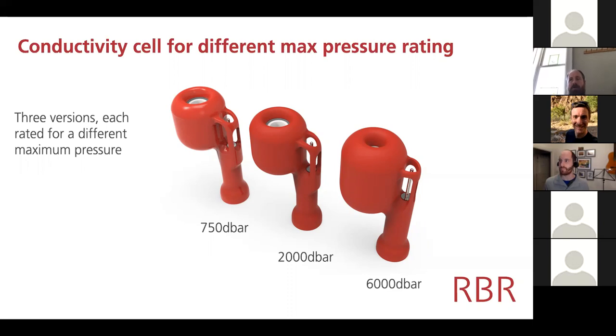Now, we do have a thermistor that's more suited to faster profiling, not to Argo. Argo at 10 centimeters per second is fine with this, the same with most gliders. But if you're going to profile at 1 meter per second or free fall at 2 to 4, 5 meters per second, then you would benefit from a faster time constant. And so we have a stainless steel thermistor string, which has a time constant that's about 10 times faster. On the data sheet, it says 100 milliseconds. In reality, it's about 70 milliseconds. All of the thermistors are within about 10% of each other. And that means that with those kinds of numbers, you don't need to individually characterize them at all. So that is really a whistle-stop tour of inductive conductivity, particularly in the RBR implementation.